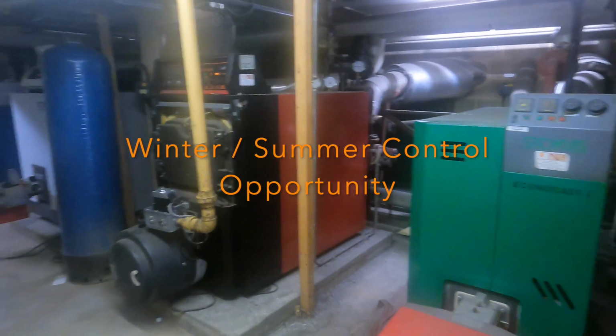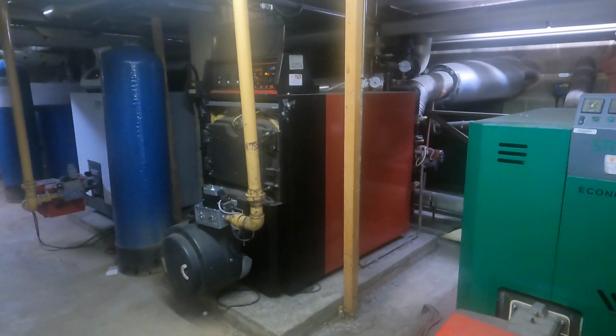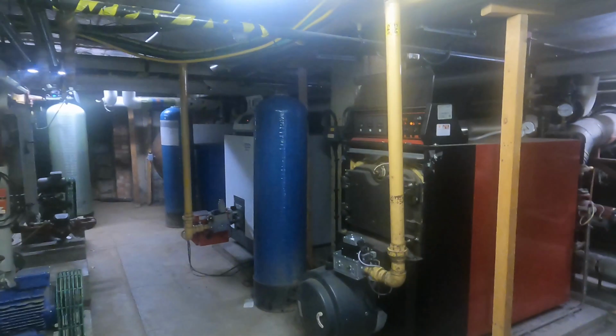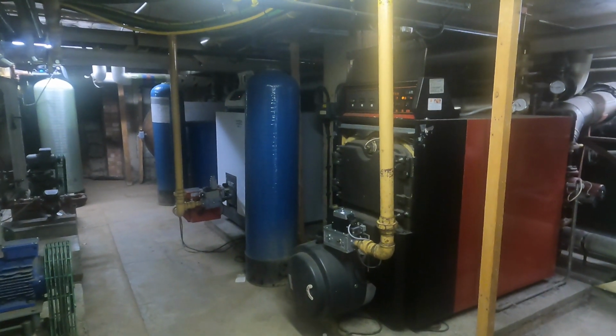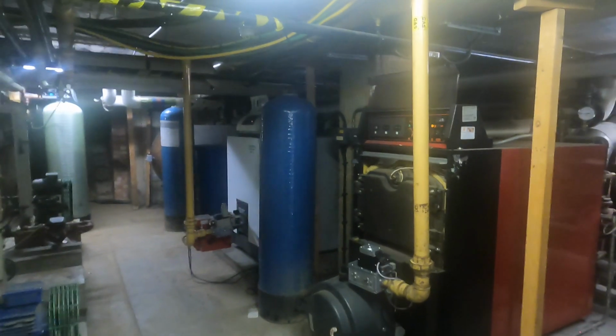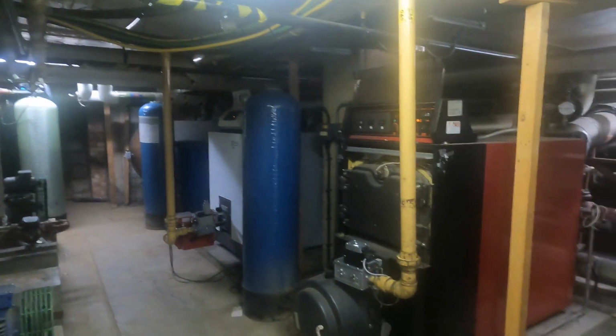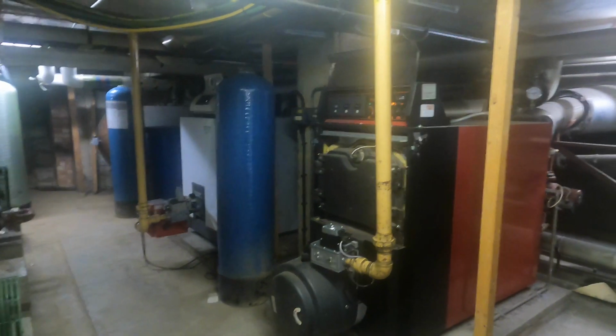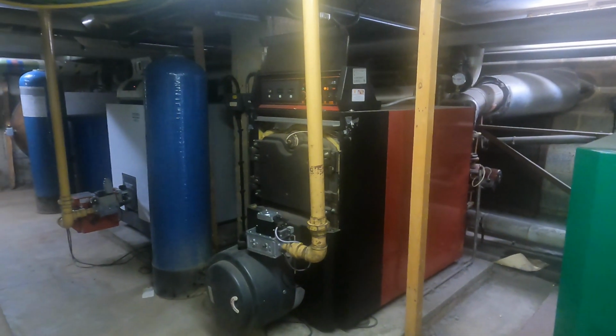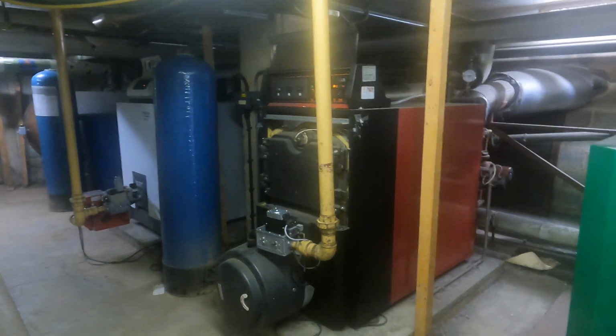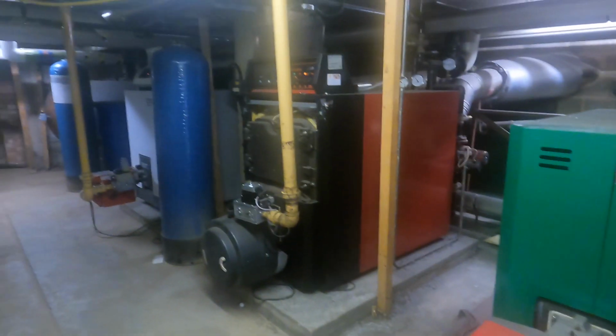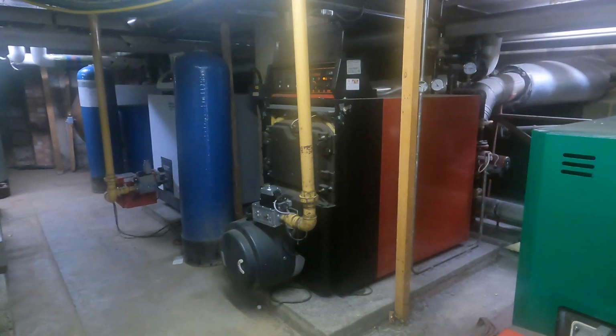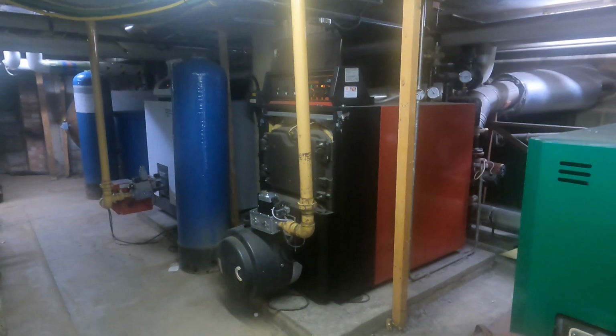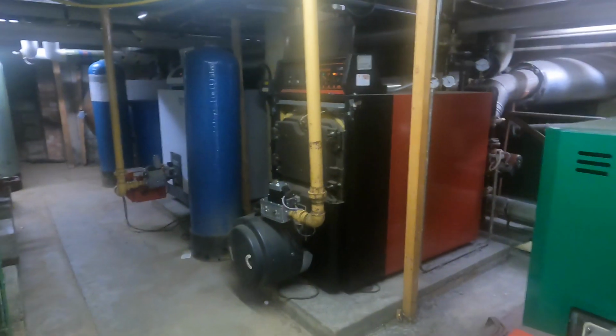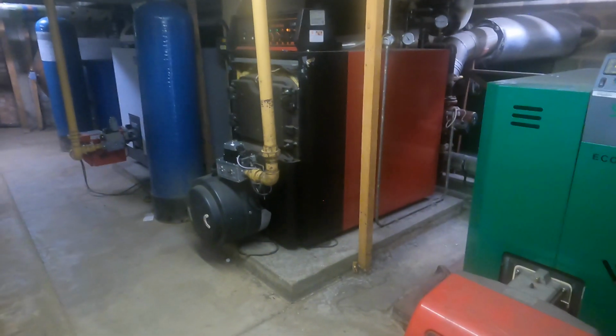The other telltale issue is we have 3 boilers here, and on the panel there's nothing to say how these boilers run. Now they should be sequenced, and we should expect that possibly one of these boilers would be the lead. So let's take number 1 boiler as being the lead boiler. That would come on. If it can't maintain the temperature, the second boiler would come on. If both boilers cannot maintain the temperature, the third boiler would come on. However, after speaking to the maintenance manager, he tells us that all 3 boilers run all the time at the same time. So we obviously have a problem regarding the control of this.